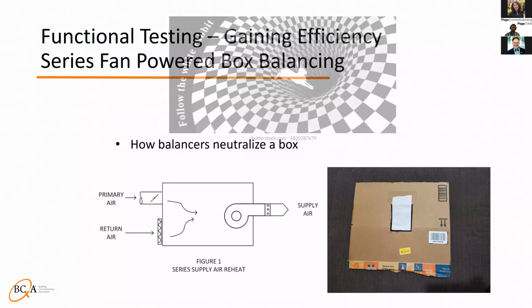So what is neutralizing? Let's go down a quick rabbit hole. Neutralizing is when balancers will adjust the fan speed on the series fan powered box until the primary air matches the fan output. After the box has been calibrated and proportioned in max cooling, the balancer will replace the filter with the meticulously calibrated and extremely expensive device you see on the right. Some may call it scrap cardboard and tissue paper. The fan speed is then adjusted until the tissue paper stays vertical. This proves that no air is entering or leaving from the return during max cooling.